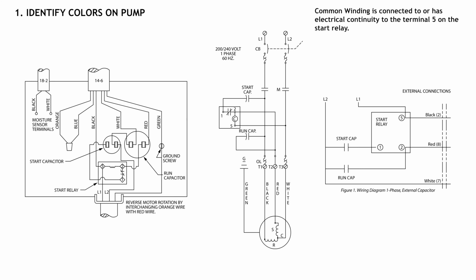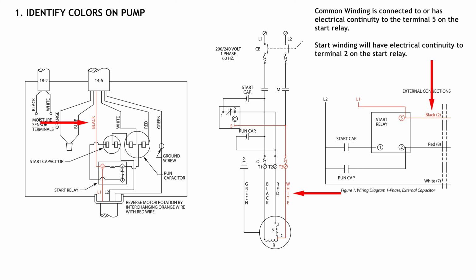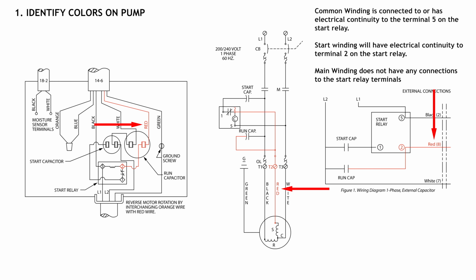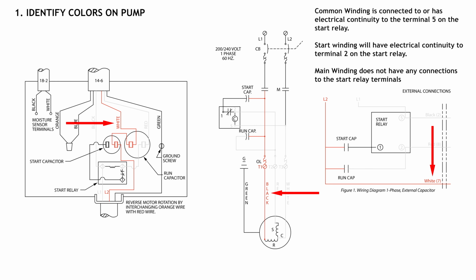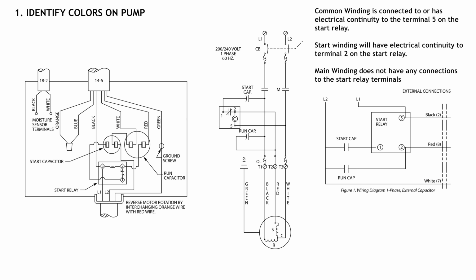The common winding will connect to terminal 5 on the motor start relay. The start winding will connect to terminal 2 of the motor start relay. Whichever winding is not connected to the motor start relay is the main winding. It is a good idea to perform the ohm meter test shown in another video to verify the identification of common, main, and start windings.